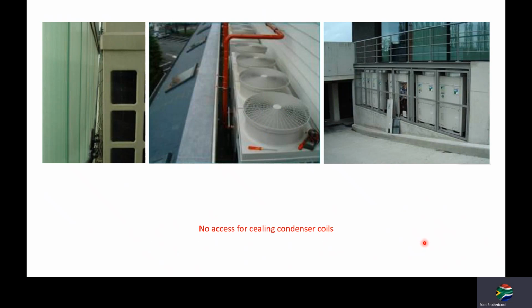Here you can see these little condensers that have been installed in rows. There's no access for cleaning any condenser coils. There's zero access. You cannot get in behind there to clean. No cleaning possible. This is ultimately going to result in high head pressures running, increased power consumption. Your electronics are going to run a lot hotter. It's also going to affect your cooling performance on the system. So always consider serviceability.